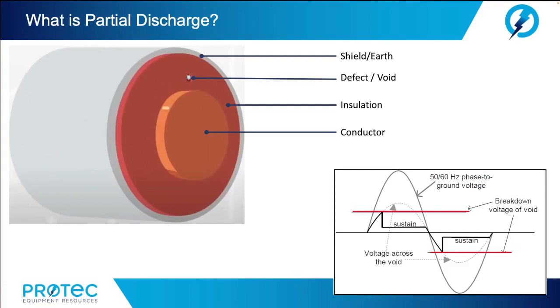Partial discharge occurs in solid, liquid, and gaseous insulation mediums. PD can also occur in the form of corona, surface tracking, or floating electrode, metal-to-metal discharges, causing degradation of the insulation. Now, once partial discharge begins, it will always get worse. The NFPA 70B, the recommended practices for electrical equipment maintenance, states that insulation breakdown is the number one cause of electrical failures.